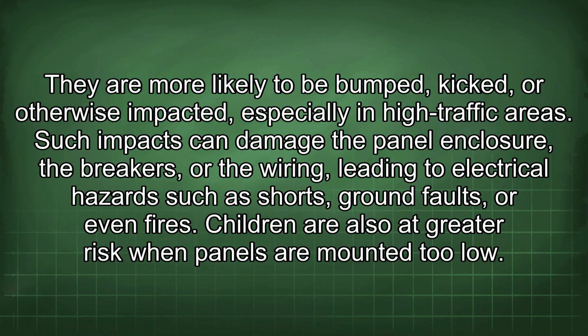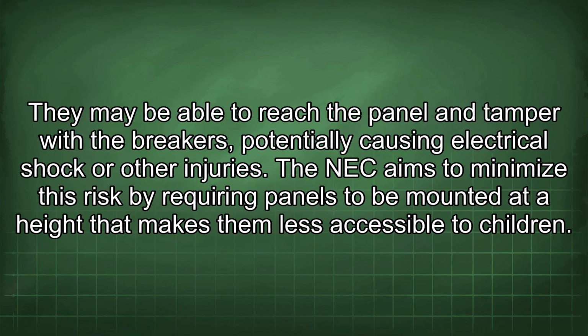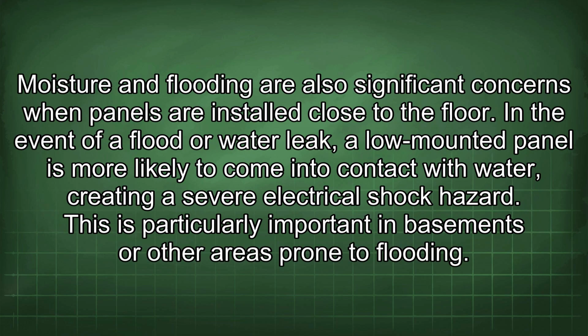faults, or even fires. Children are also at greater risk when panels are mounted too low. They may be able to reach the panel and tamper with the breakers, potentially causing electrical shock or other injuries. The NEC aims to minimize this risk by requiring panels to be mounted at a height that makes them less accessible to children. Moisture and flooding are also significant concerns when panels are installed close to the floor. In the event of a flood or water leak, a low-mounted panel is more likely to come into contact with water, creating a severe electrical shock hazard. This is particularly important in basements or other areas prone to flooding.